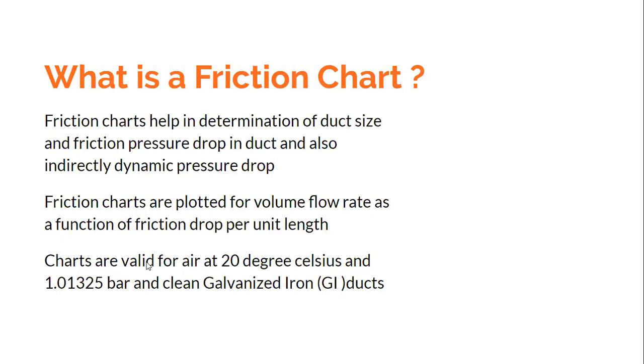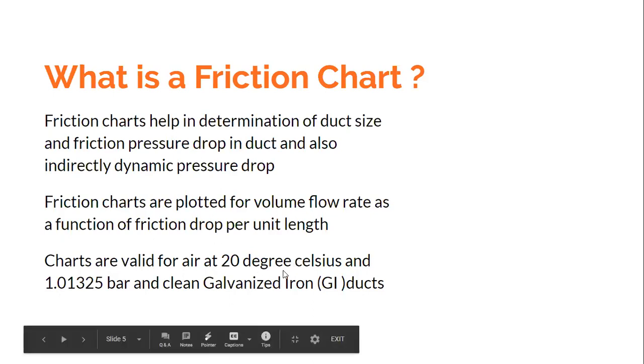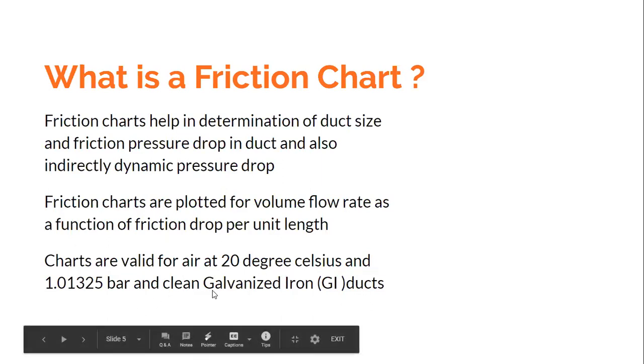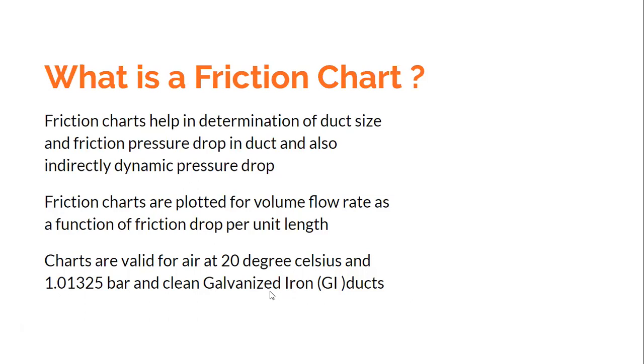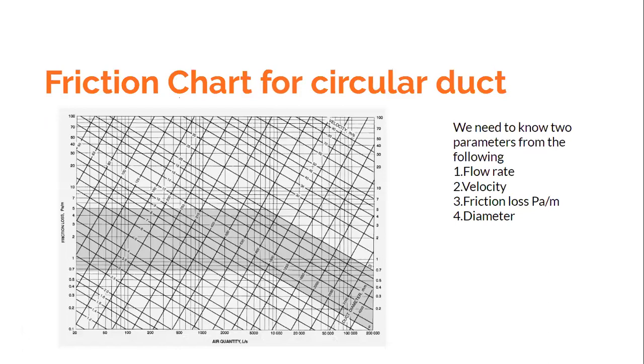The friction chart I am going to show is valid only for air at 20 degrees Centigrade and at a certain pressure — that means at a certain specific volume. It is valid only for ducts that are clean and made of galvanized iron. If you are using a different material, different temperature, or different pressure, appropriate corrections are suggested, which is not a great difficulty.